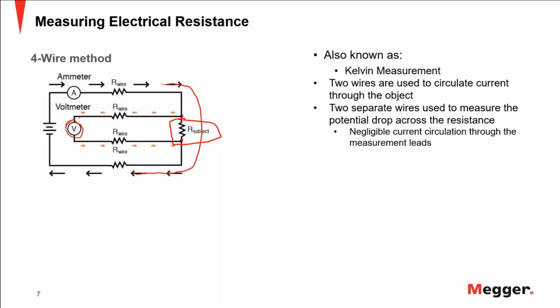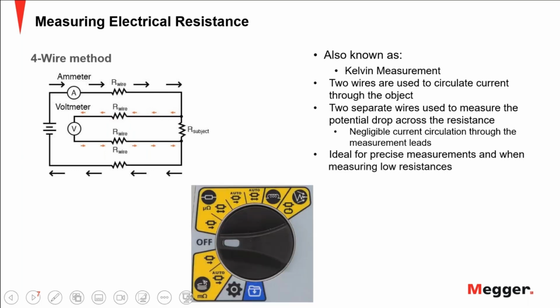And because voltmeters have a very high impedance, the current that is going to circulate through these wires is very little. So really, you are measuring the voltage at the terminals of the resistance that you want to measure. So that is going to give you a much more accurate value. You need four wires, two for the current and two for the voltage measurement, for the voltage drop. And with this, you get precise measurements, and typically you see this represented in the instruments with a little rectangle and two conductors, like it is shown here.